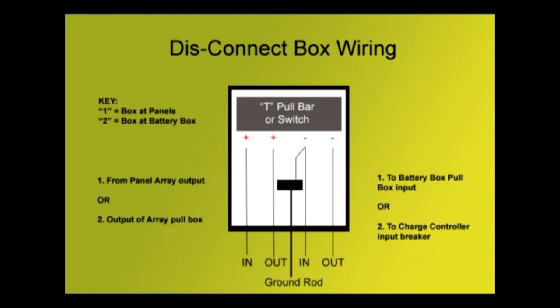These are, number 1, the pull box at the panel array, or number 2, the box at the battery box, at the other end of the wire coming from the array up to the battery box. For number 1, your positive and negative in and out would be coming from the panel array output, positive on the far left, going out to the battery box pull box input. For number 2, that's the output of the array pull box, coming on the wire from the arrays, positive going into the connection on the far left, and output number 2, the red one plus, to the charge controller input breaker.